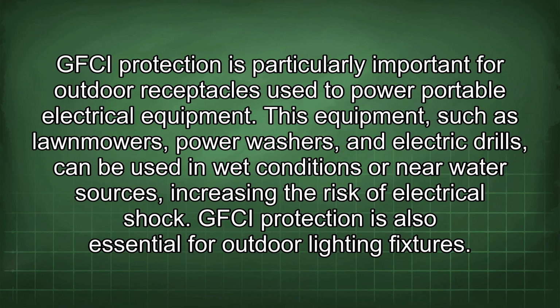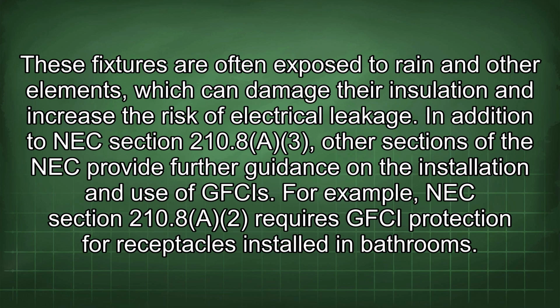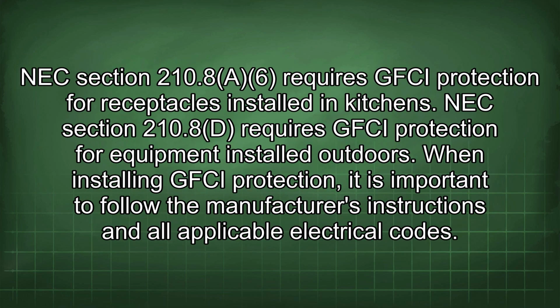GFCI protection is also essential for outdoor lighting fixtures. These fixtures are often exposed to rain and other elements, which can damage their insulation and increase the risk of electrical leakage. In addition to NEC Section 210.8A3, other sections of the NEC provide further guidance on the installation and use of GFCIs. For example, NEC Section 210.8(A)(2) requires GFCI protection for receptacles installed in bathrooms. NEC Section 210.8(A)(6) requires GFCI protection for receptacles installed in kitchens. NEC Section 210.8D requires GFCI protection for equipment installed outdoors.